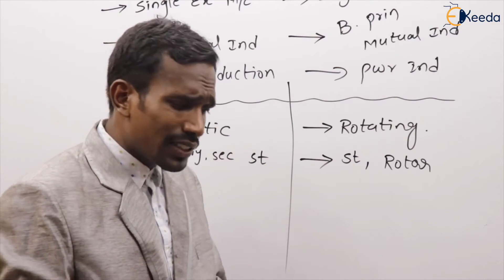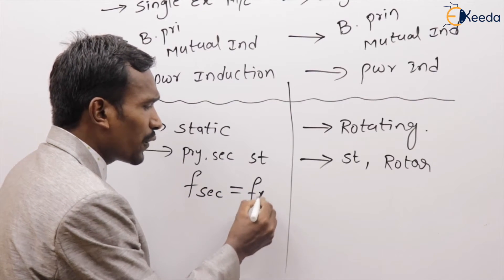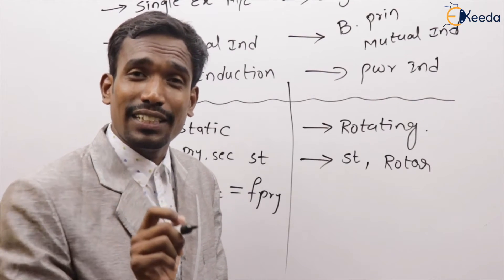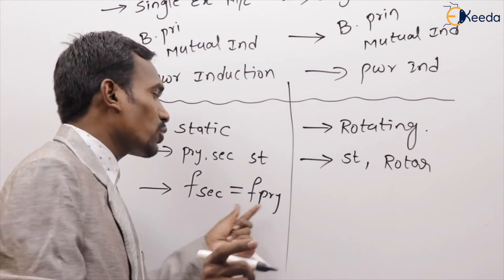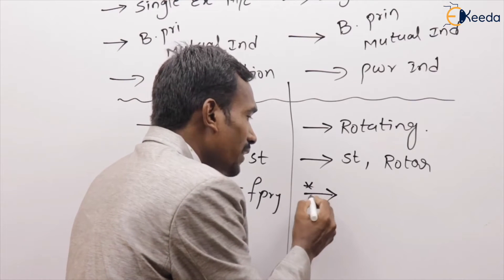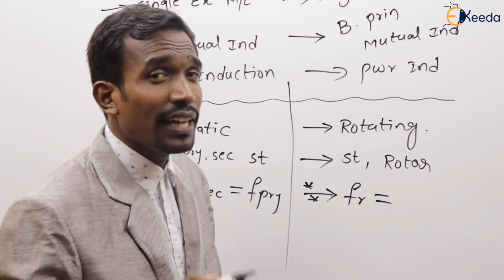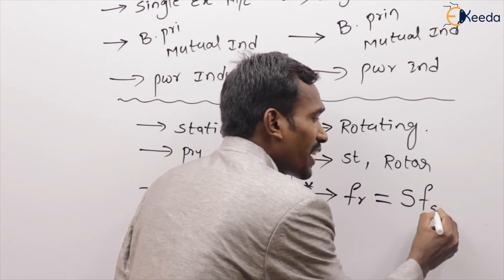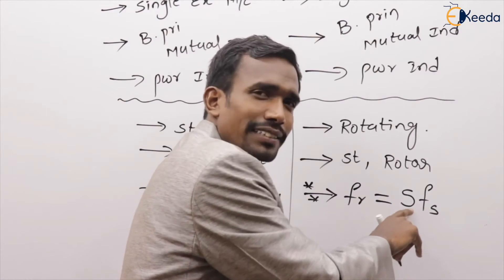Another difference: in the transformer, the frequency in the secondary circuit is exactly equal to the frequency in the primary circuit — that is why it is called a constant frequency device. Whereas in the induction machine, the rotor frequency is not equal to the stator frequency; instead, rotor frequency equals slip times the stator frequency.